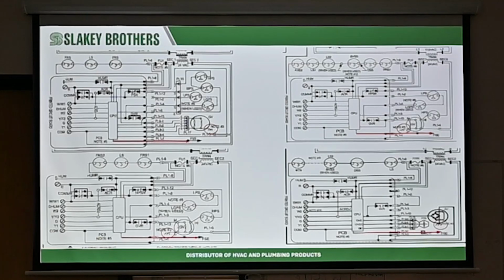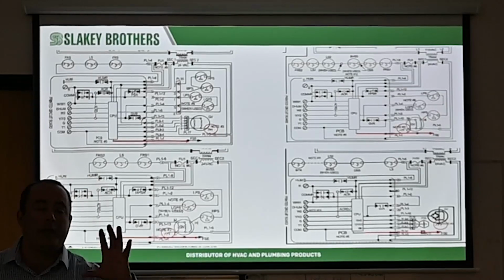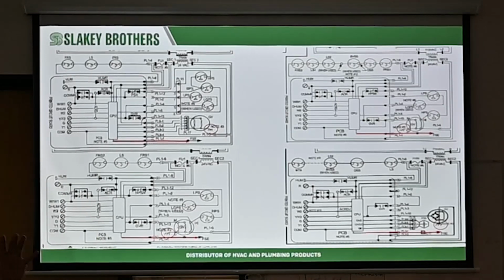When there's enough negative pressure, that's what it says, negative 0.68 plus a 0.15 more on it. When it reaches that negative pressure, it closes that switch and it stays closed, as long as that negative pressure is always there. So it'll open on pressure rise over here. This means it'll open on pressure rise. This one means it'll open on pressure fall. So all this means overall, it is a defaulted open switch. These pressure switches are always open until pressure is applied to them. Positive gas pressure closes that safety switch. Negative pressure in the inducer assembly closes that safety switch and allows the heater itself to work.